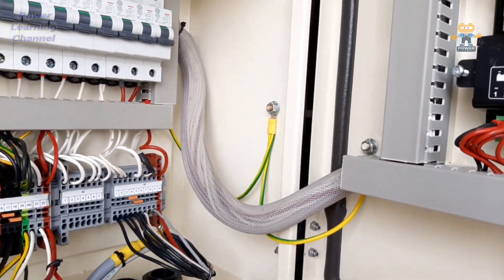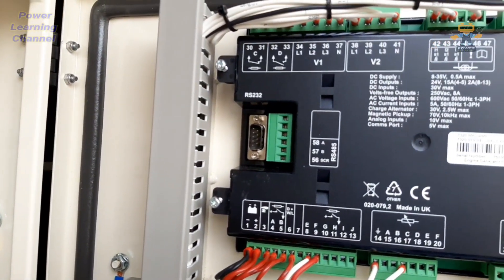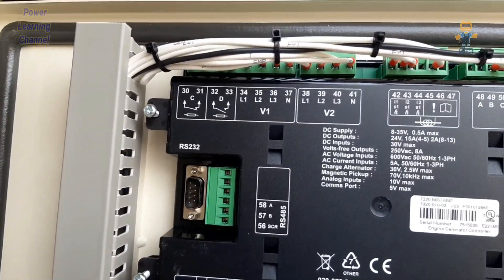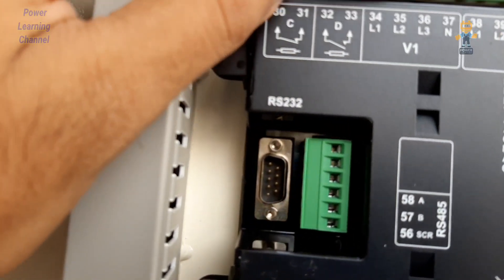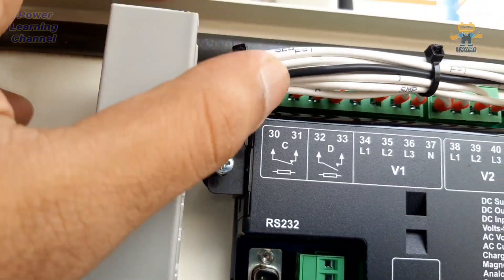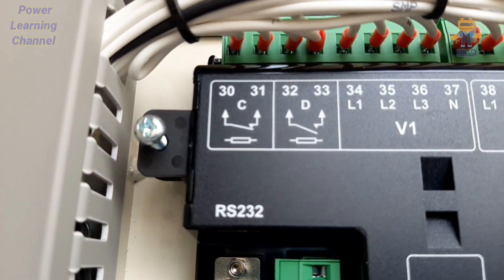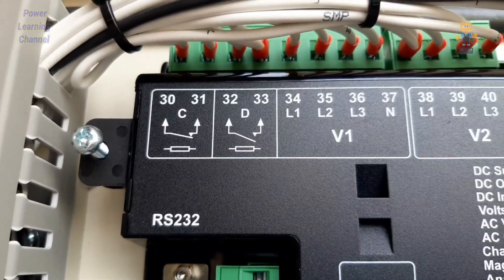The grounding terminals are also connected here. We have our Deep Sea DSE 7320 controller. On the left-hand corner, terminals 30, 31, 32, and 33 are volt-free contacts — you can use them in any application. Here we are using them for ATS panel control. From 34 to 37 — this is V1, the generator sensing voltage.